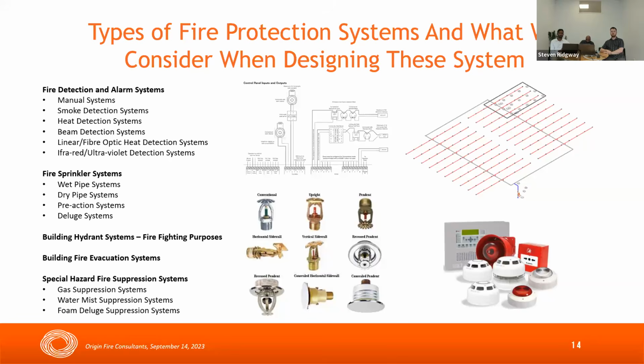A fire detection and alarm system encompasses an evacuation system. Typically in buildings, the evacuation occurs throughout the building simultaneously. So there needs to be an adequate level of coverage of alerting devices for the occupants. In certain situations, audible alerting devices or speakers are accompanied with visual alerting devices such as strobes. And in some cases, buildings have staged or phased evacuation systems, where certain levels or floors may evacuate prior to others.